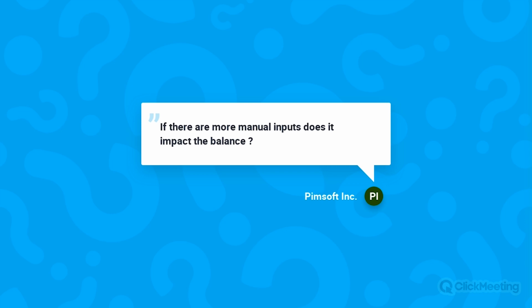If you are targeting performance monitoring, you should ensure that all the data comes automatically and straightforwardly to feed the model, because nobody will be in front of the Sigmafine screen looking at the model. It's a really different way of use compared to production accounting, so in that sense you should not even have manual inputs. If you run instead a daily steam balance, maybe yes, you are allowed to do some manual inputs because you have the time to do so.